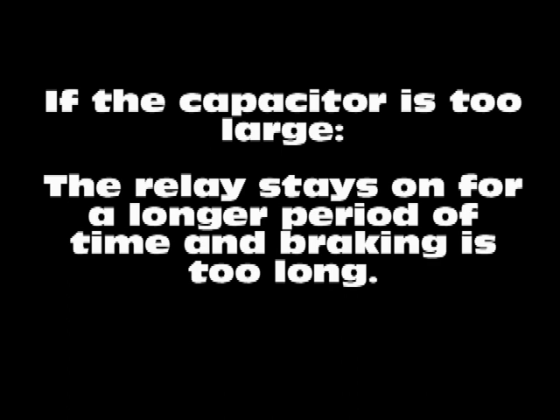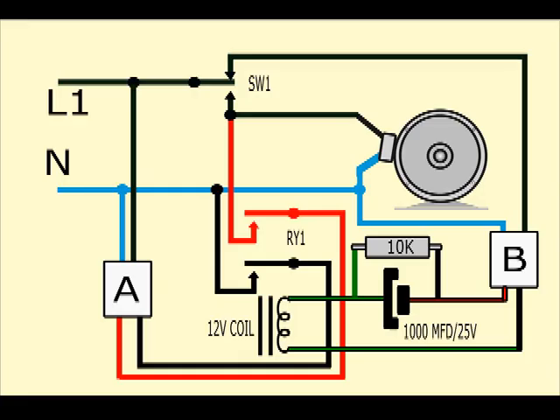If the capacitor is too large, the braking time may be too long. In both cases, power supply labeled A can overheat and become damaged.